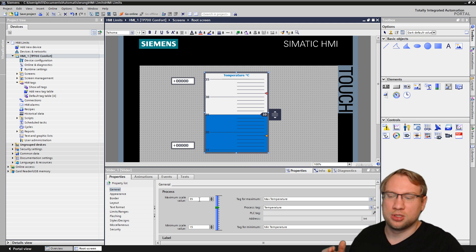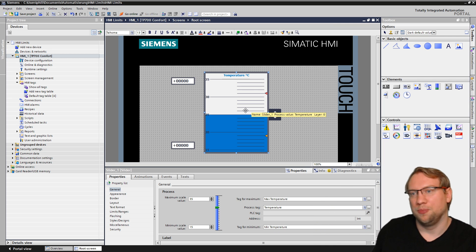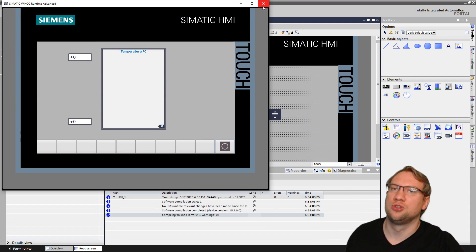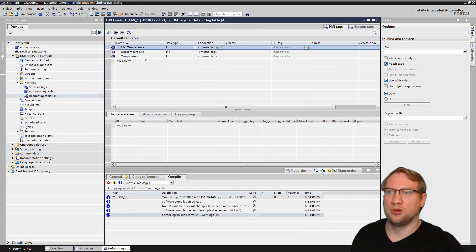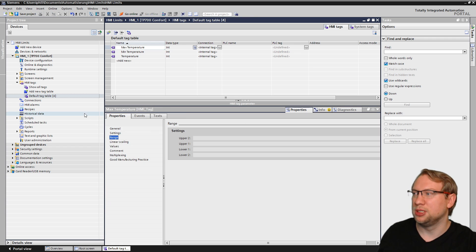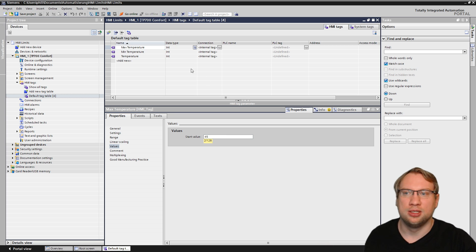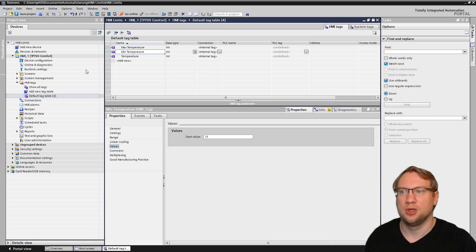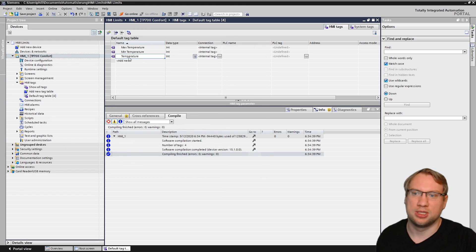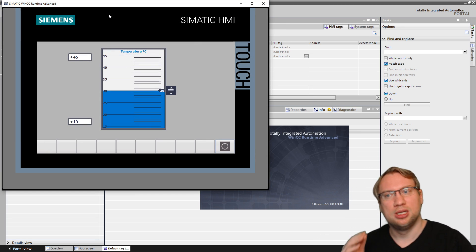Those min/max tags can also be driven from the PLC — they need to be integer values though. The next thing is: it's a bit annoying that when you restart, everything starts at zero. We can set a start value. I go to my tag table, select maximum and minimum temperature, go to Properties > Values, and set a start value. Maximum temperature should start at 45 and minimum at 15 to avoid that problem. I'll also set the temperature tag to start at 30, so it begins somewhere in the center.